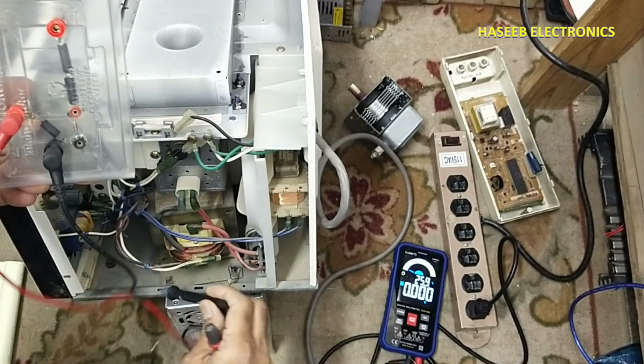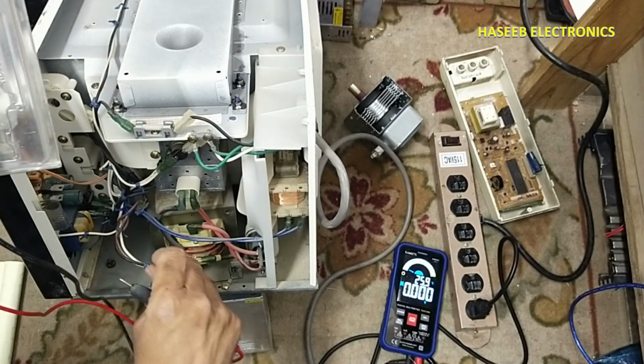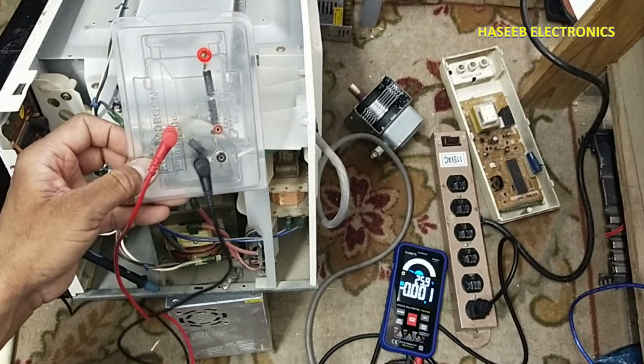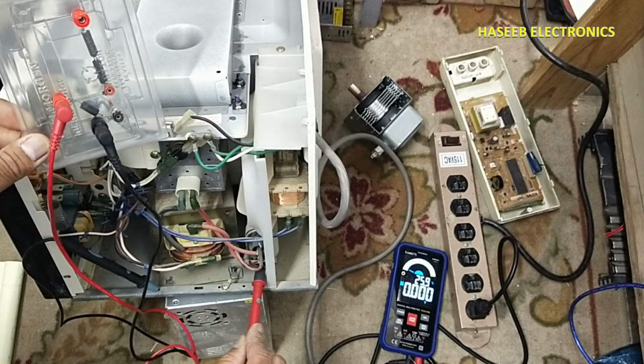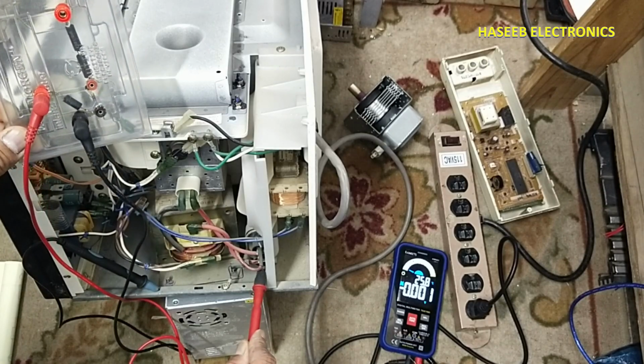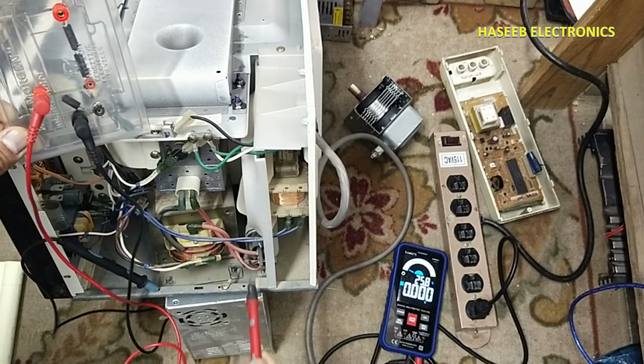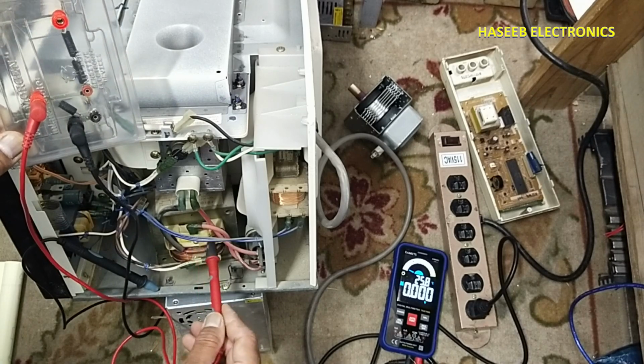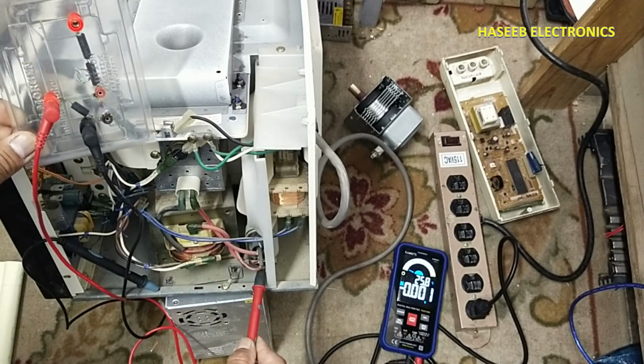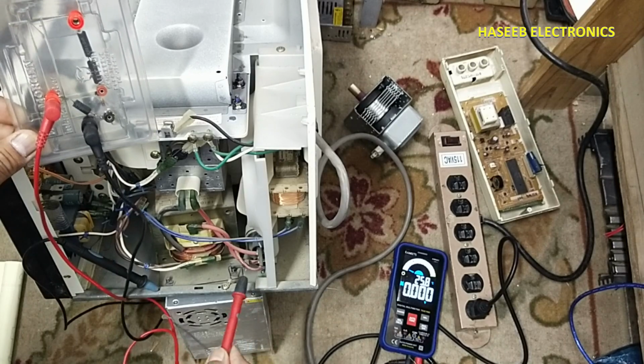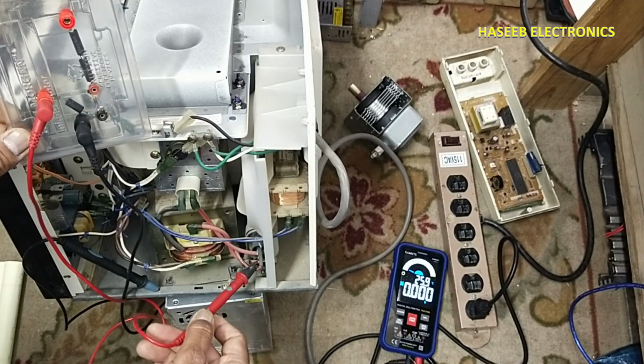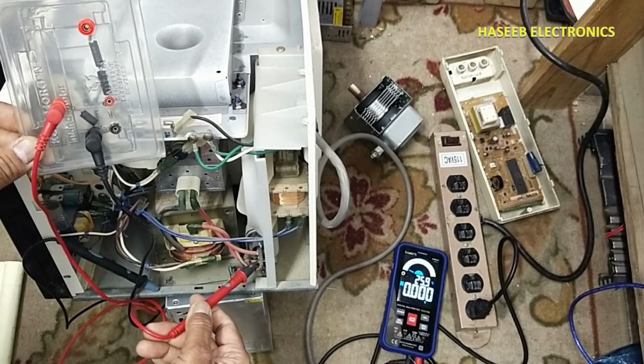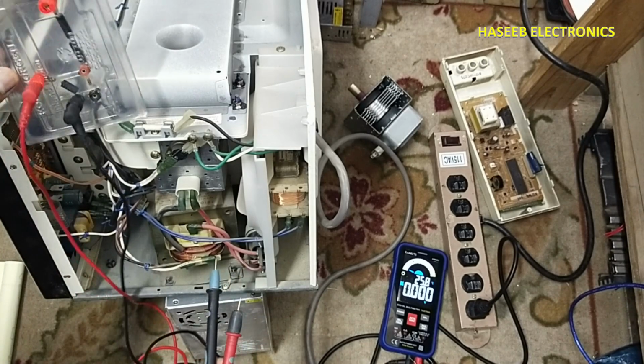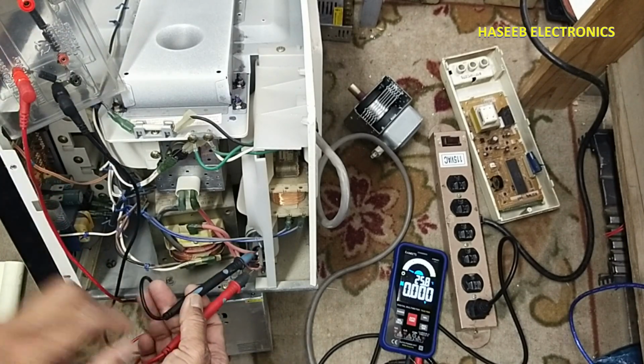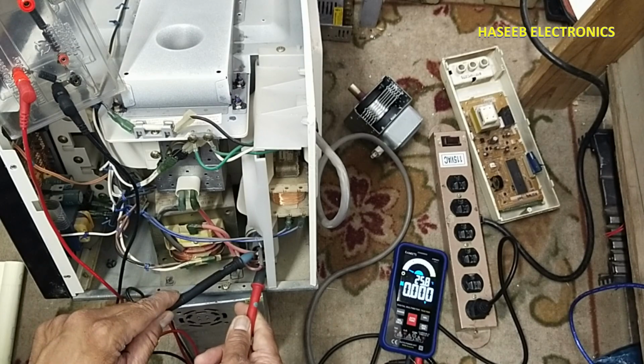To discharge this capacitor, we can connect one lead to the chassis here, and we will connect to the one end, the end that is connected to the transformer, that is normally connected to ground through this transformer winding. So for safety we can discharge it. The most important point, that is the other side of this capacitor, connect it here, and for more safety we can connect to both terminals.